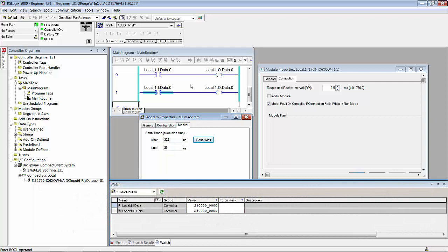Every once in a while we might see it flicker. I'm not seeing it flicker at all. Oh, there it just did. But I'm not hearing it because the state is changing for such a short period of time that the relay contacts don't have time to energize. If I look at the output LED on the I/O module, I may or may not ever see that output flicker on. I just saw a tiny flicker.